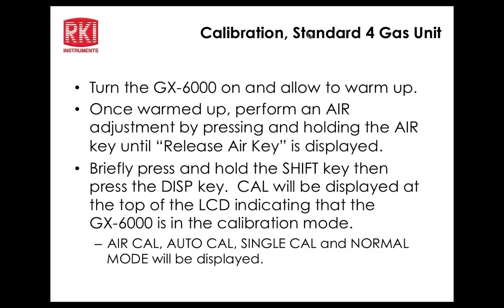Okay, now single cal is very simple. It's just taking 1 gas at a time. And I just want to mention something really quickly, guys. The reason John was able to do the 4 sensors plus the isobutylene right away was because we're using our 5-gas mixed cylinder that has the standard 4 gases plus isobutylene. Good point. So if we had 2 cylinders, a standard 4 gas and then a separate isobutylene cylinder, at the conclusion of the 4 gas is when you have the opportunity to switch your cylinders to the isobutylene and then continue in the menus the same way that I did. Okay?